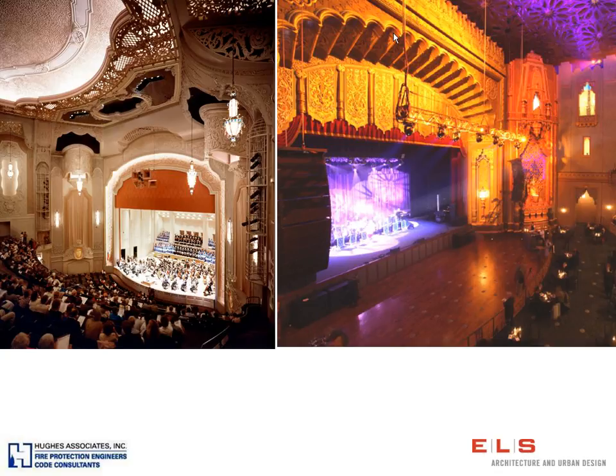And an important thing to bring out is when do sprinklers become most effective. These are 2 other theater projects we did. The Portland Theater, which is now the Schnitzer Concert Hall up in Portland, and the Oakland Fox. And both of these have really quite different adaptive reuses. But one thing that is common to them is the distance from the floor up to the ceiling. And so in both cases, it was analyzed how effective sprinklers would be.